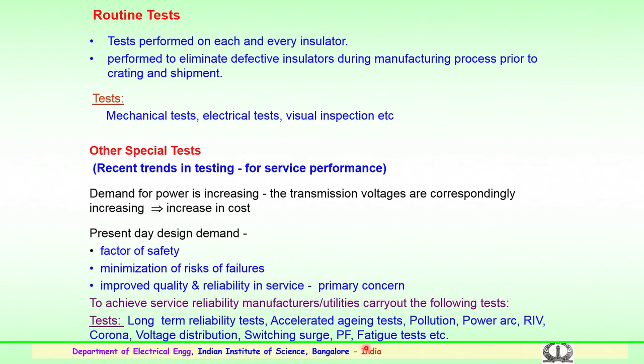The contamination or pollution test was introduced later, after the extra high voltage or ultra high voltage ranges, the power arc test, radio interference voltage measurements, the corona test, voltage distribution across the string of ceramic or glass insulators, switching surge, power frequency, fatigue test. These are all tests which have come up after the voltage levels being used for extra high voltage and ultra high voltage, to take special care, to see the safety and to minimize the risk of failures. These tests have been included, and are essentially carried out for the equipment used for extra high voltage and ultra high voltage ranges.